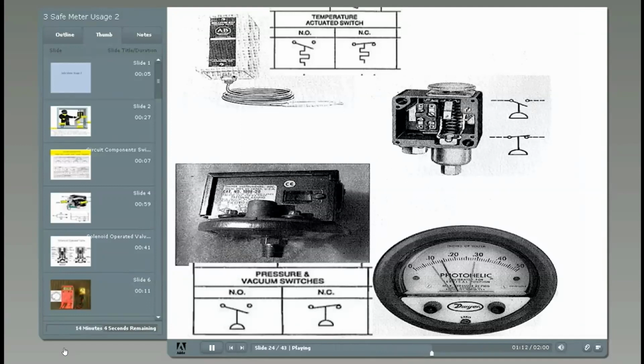The device at the bottom left is also a pressure switch. It can be used to monitor the operation of the blower at the burner. The normally open NO contact will close at the selected pressure, and the normally closed NC contact will open at the selected pressure. The photohelic device at the bottom right is a very sensitive air pressure switch. It can be used to monitor suction at the front of the dryer. This can be used to open and close the damper automatically.